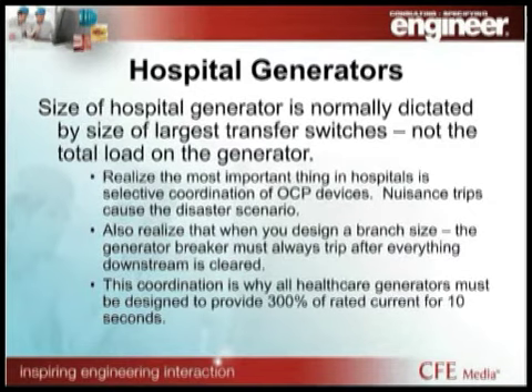So this is one of those bold statements that will probably get me a couple texts and emails, but I can't stress enough that the size of a hospital generator is normally not driven by the load in the hospital. It is driven by the size of the largest transfer switch. And this may not be immediately obvious, but realize the most important thing in hospitals is that you coordinate your circuit breakers, selectively coordinate them, and the size of the largest branch that you serve is probably your chiller, if you're going to put that on the generator, or another equipment branch. Your overcurrent protection for your generator cannot be any smaller than that branch. So no matter what all the loads add up to, you've still got to have a larger overcurrent protection device on your generator than the largest transfer switch that you've got sitting out there.